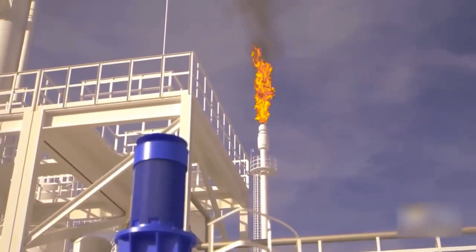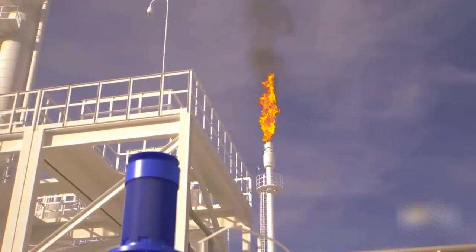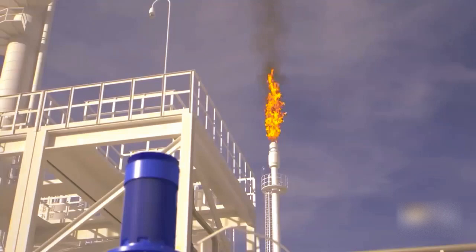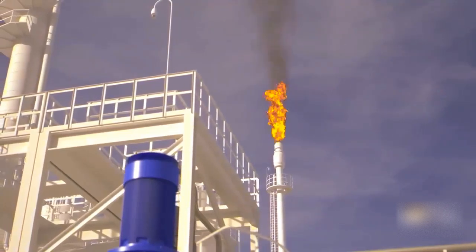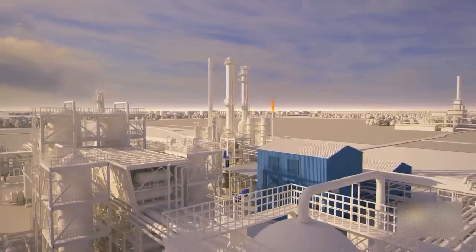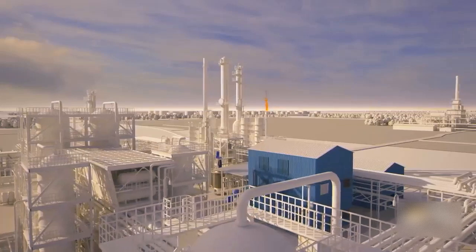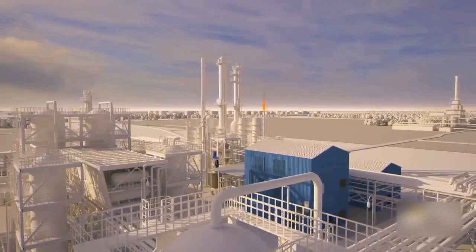The board operator was concerned about exceeding environmental emissions limits for the flare. As a result, he did not fully open the pressure control valve. He was also focused on other start-up activities, and did not realize the valve was not open as much as it needed to be to bring the pressure under control.